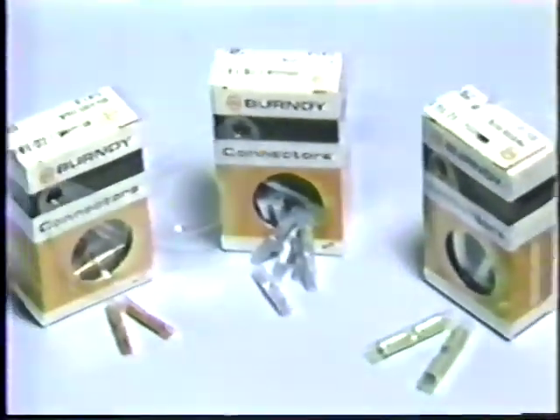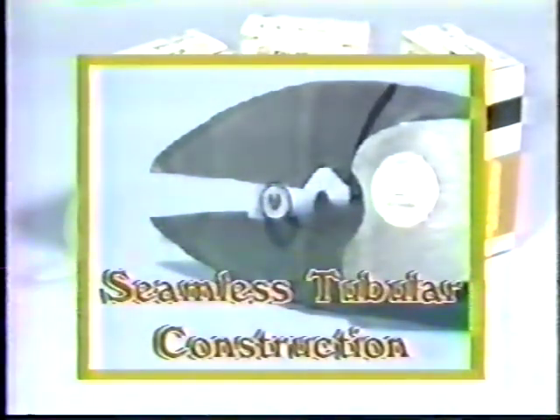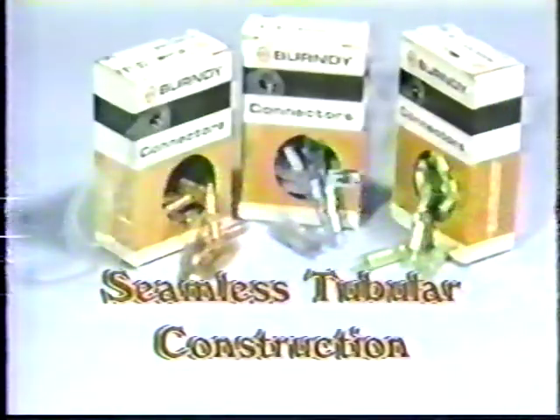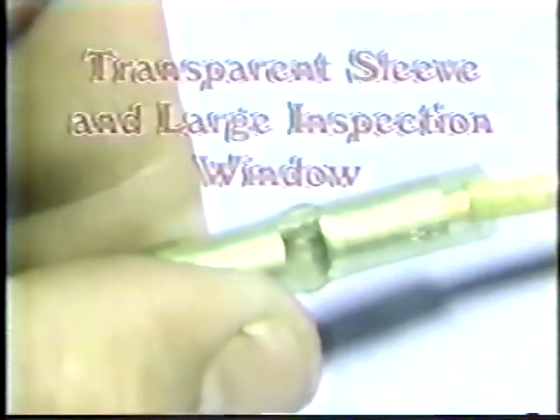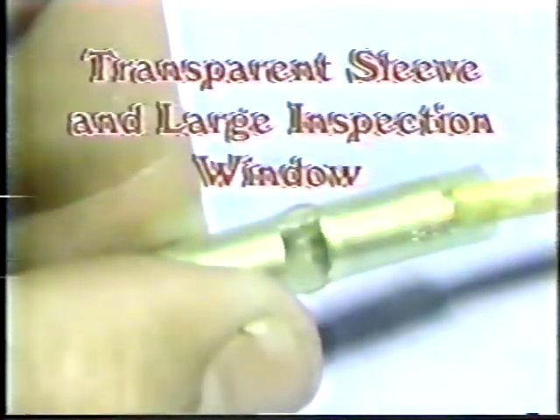Burndy's nylon insulated splices feature a seamless tubular construction and positive insulation grip. Unlike butted seam designs, Burndy splices can be crimped anywhere around the barrel without concern of splitting or folding seams. These splices also feature a transparent sleeve and large inspection window, enabling the electrician to easily inspect wire insertion. For applications that don't require a positive insulation grip, the economical YSE splices can be specified.